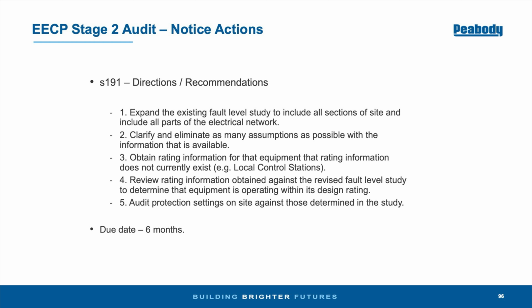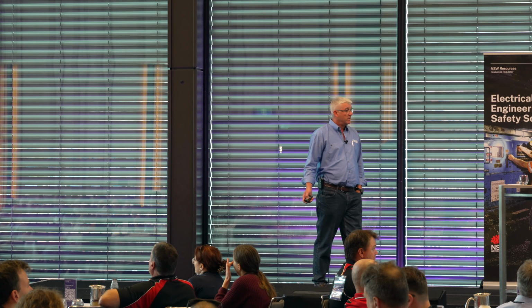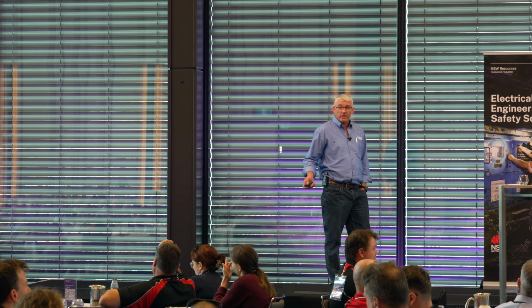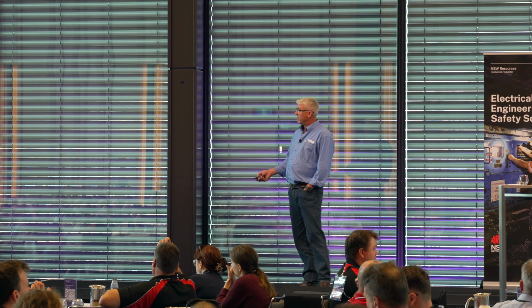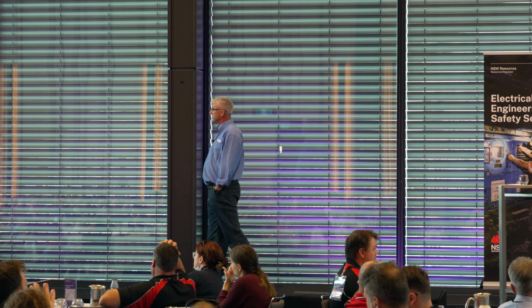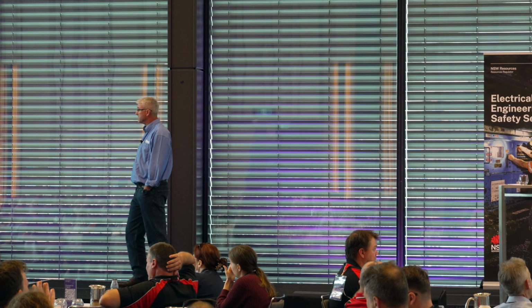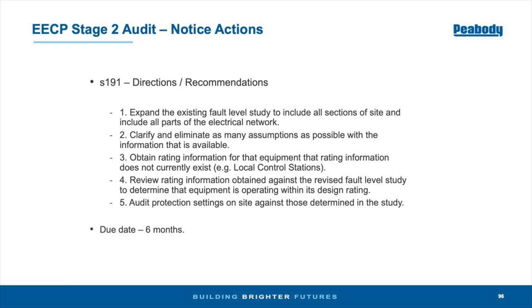Clarify and eliminate as many assumptions as possible. Prove what you've got, have a look at what you've got and make sure that's what you've based it on. Obtain rating information for that equipment, because that rating information doesn't currently exist. If you've got something in the network you're using, you should know what fault level it's at, say an LCS switch, because some of the stuff out there isn't provided. Review the rating information obtained against the revised fault level study.